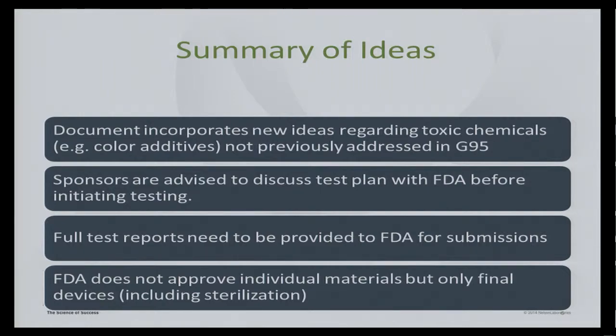And if you were here in my last talk, we talked about colorants. And right now the FDA has a huge concern with colorants. So if you are going to add a colorant to your device, please think about it, because the cost it's going to take to be able to show that colorant's safe is going to be quite large. So if it's beneficial enough to overcome that initial cost, then we can do it. But think about how beneficial it is.